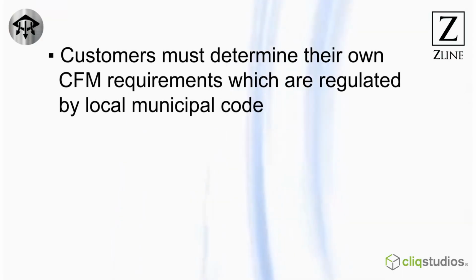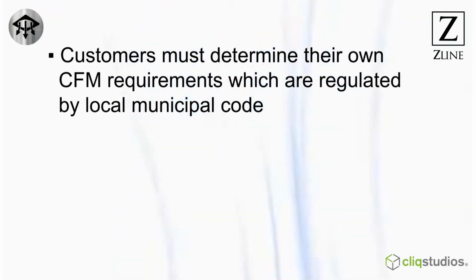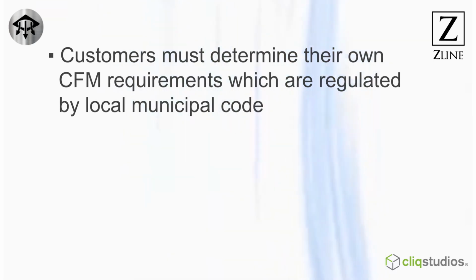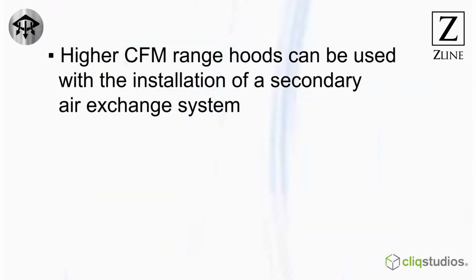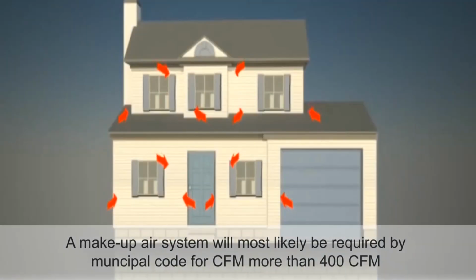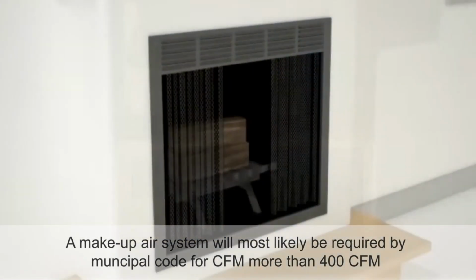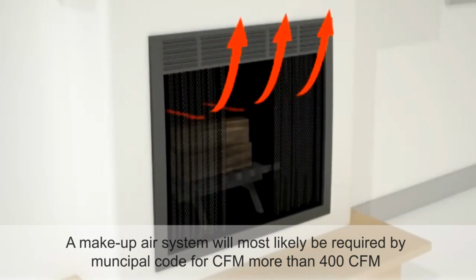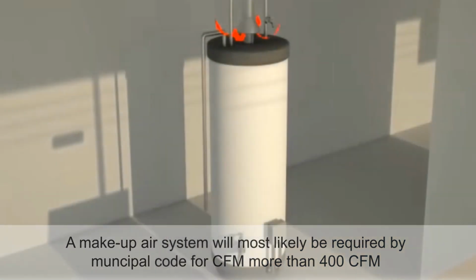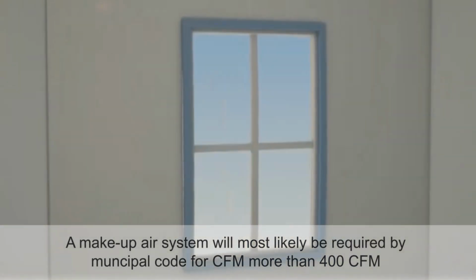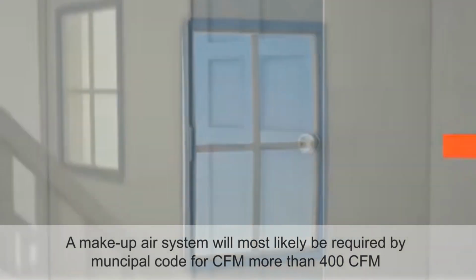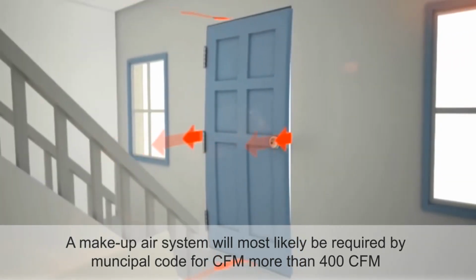Customers must determine their own CFM requirements, which are regulated by local municipal code. Higher CFM range hoods can be used with the installation of a secondary air exchange, again regulated by all the above factors. With no controlled makeup air, outside air can make its way into homes through undesirable locations with undesirable consequences. For instance, backdrafting from naturally vented combustion devices like fireplaces and water heaters can bring in harmful gases, smoke, or particulates. Air drawn in through windows and doors can result in drafts and window condensation, and outside air rushing between vapor barriers can cause potential mold problems.